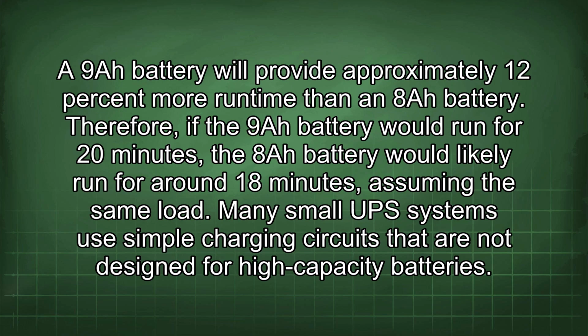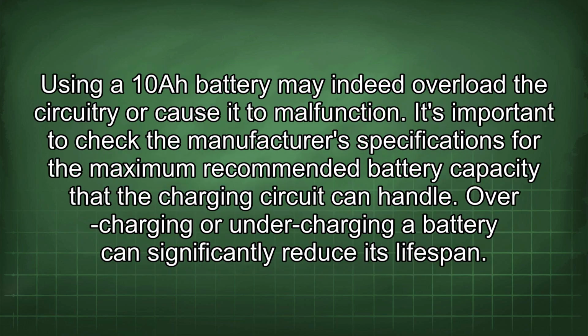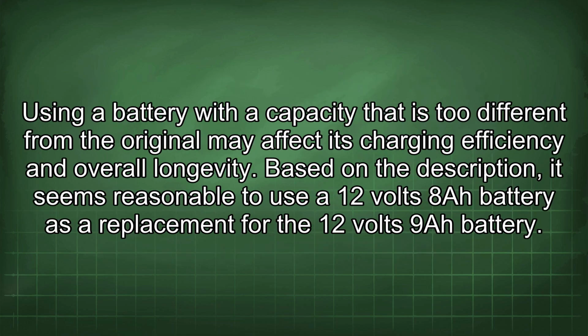Many small UPS systems use simple charging circuits that are not designed for high-capacity batteries. Using a 10 Ah battery may indeed overload the circuitry or cause it to malfunction. It's important to check the manufacturer's specifications for the maximum recommended battery capacity that the charging circuit can handle. Overcharging or undercharging a battery can significantly reduce its lifespan.